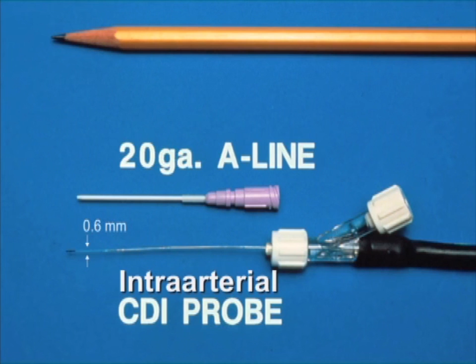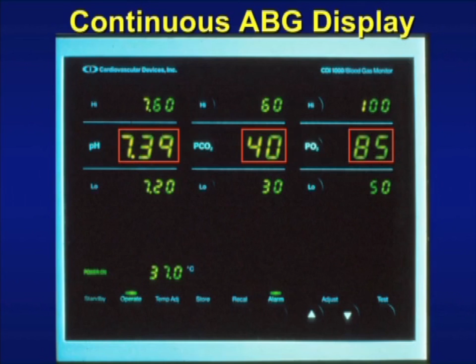But not only does it measure PO2, they have other dyes that are sensitive to hydrogen ions. So you have the PO2 being displayed here from the pyrene butyric acid that I told you about, but you have another dye, I don't remember what it's called, that measures hydrogen ion, and so you display the pH. And if you can measure hydrogen ion, as John Severinghaus showed us, you can also measure carbon dioxide tension. And so, gee, this looks a lot like a blood gas machine, doesn't it? It's giving me pH, PCO2, and PO2, but it's in real time, like pulse oximetry, telling me now what's happening now, and it's continuous. You can watch this thing change second by second. And you think, wow, I must have one of those in every operating room, right?